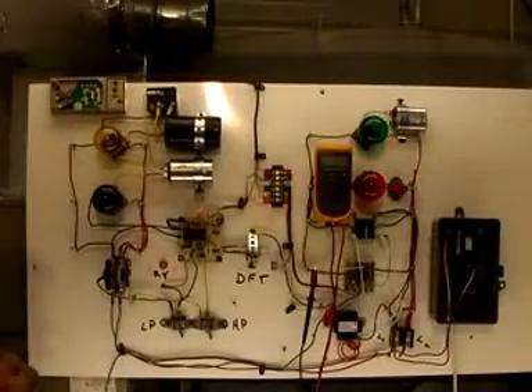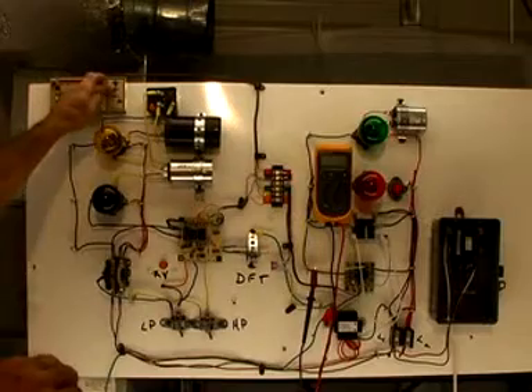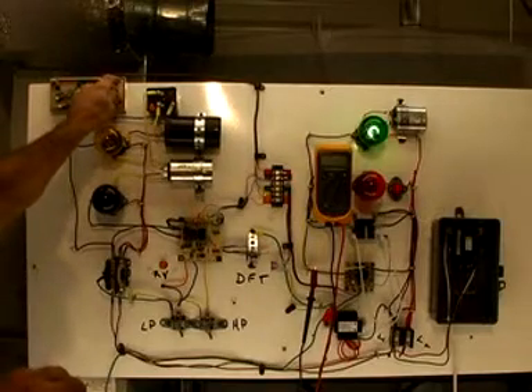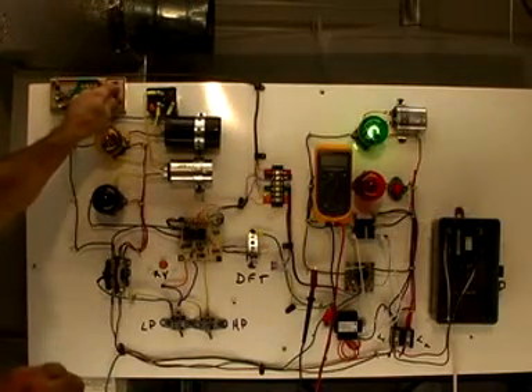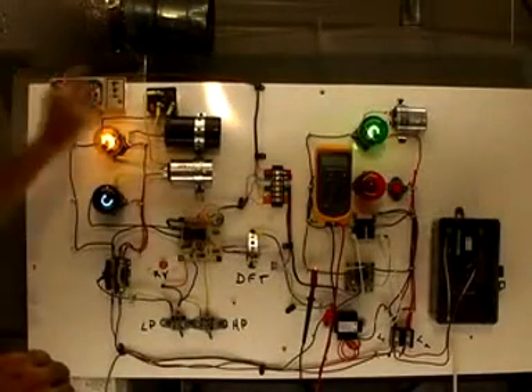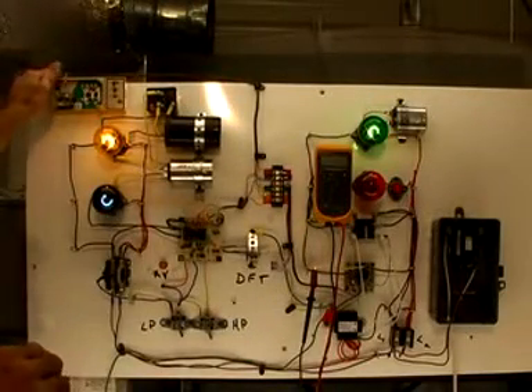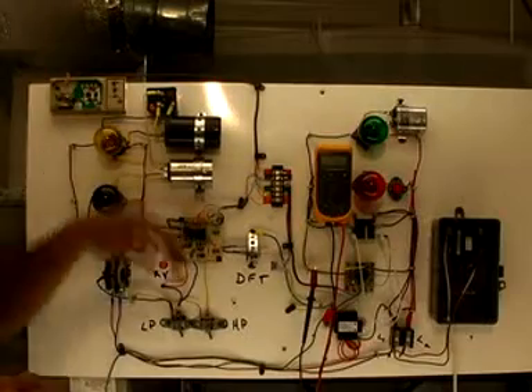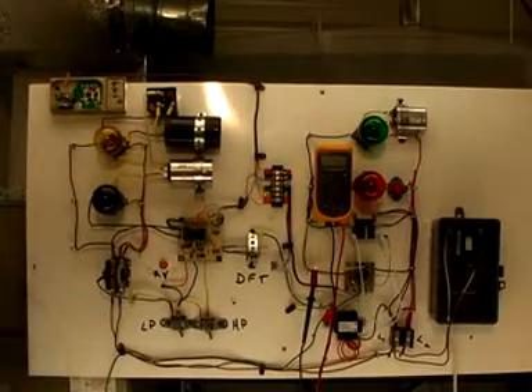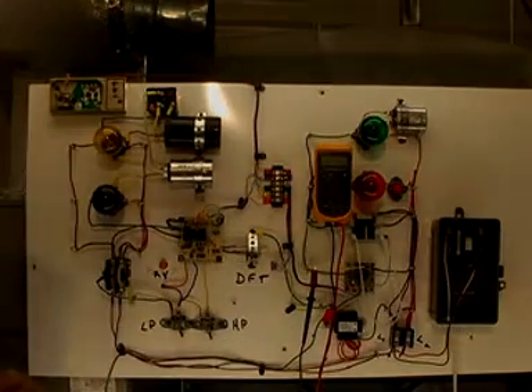Okay, I'll run the thermostat and you watch the lights. First of all, we're going to flip the fan switch to on, and the blower came on, so we know that circuit's okay. Already eliminated all those. Now I'm going to call for second stage heat, and you watch the fuse. I don't know if you can see it or not. So, looks like something wrong in our second stage heat circuit.